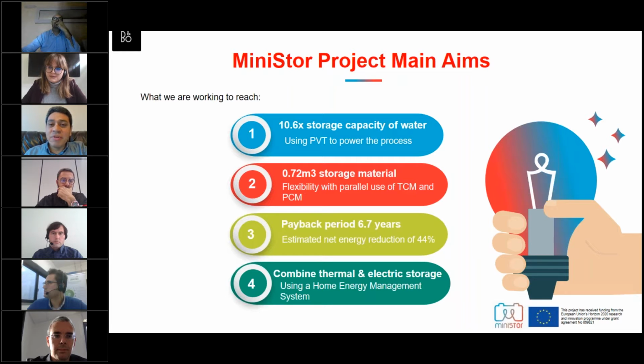What are the main aims and what are we working for? We are trying to reach 10.6 times the storage capacity of water, and we are using photovoltaic thermal panels to power the process. Since the call was asking for less than 1 cubic meter of storage material, we have calculated that with a total of 0.72 cubic meters of storage material, we can have flexibility for storage using parallel TCMs, thermochemical materials, and PCMs, phase change materials. The payback period is estimated at 6.7 years by achieving an energy reduction of 44%.